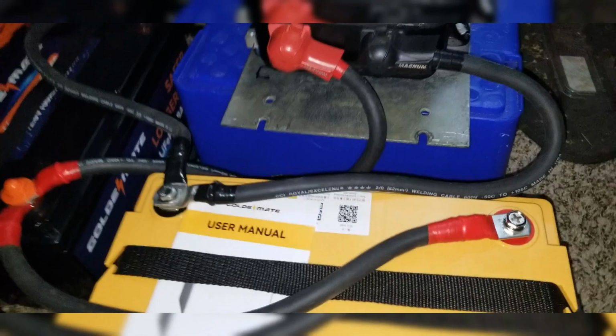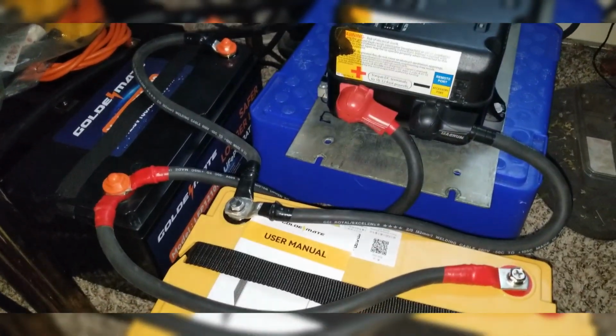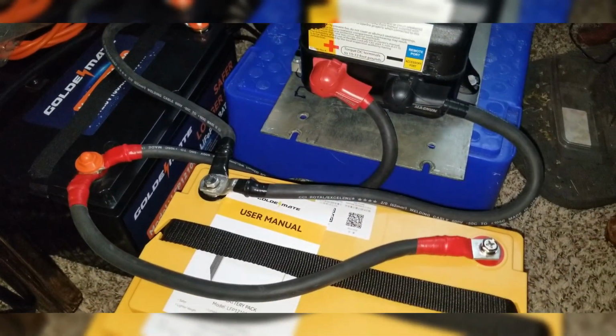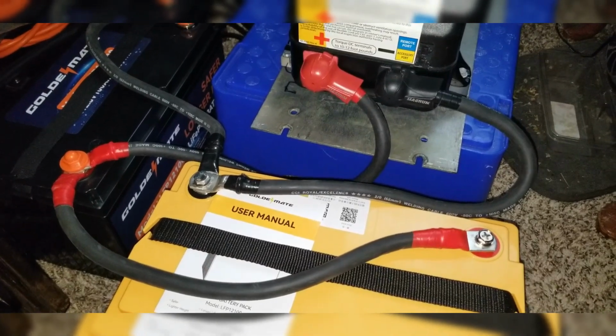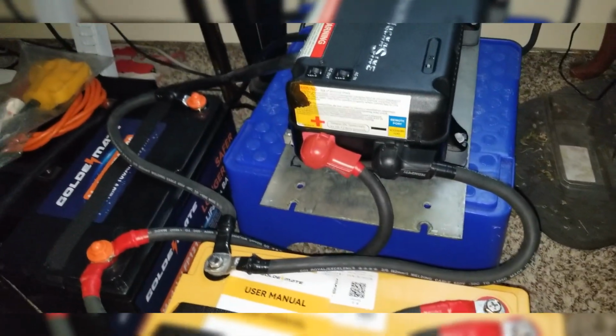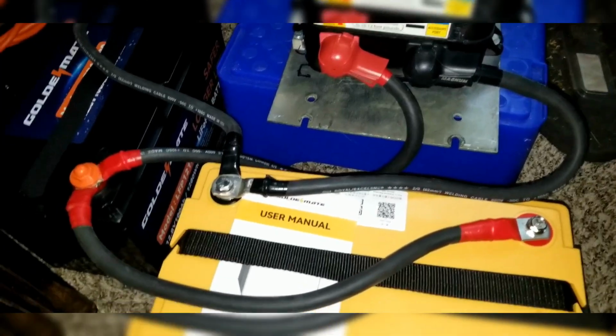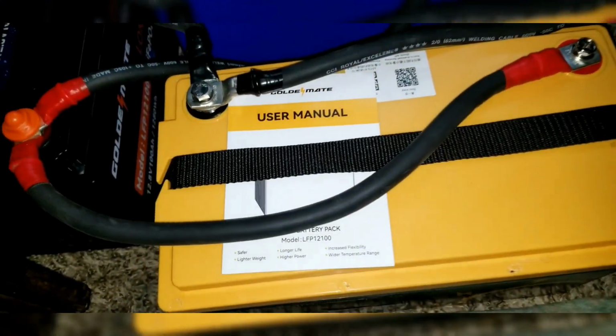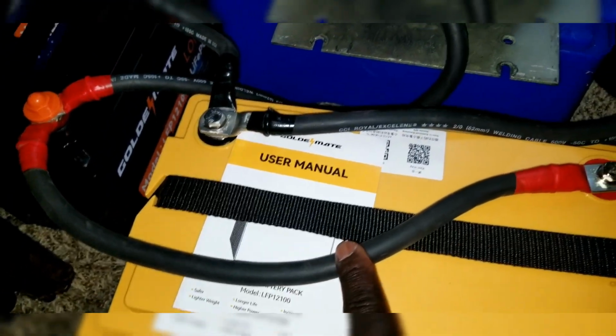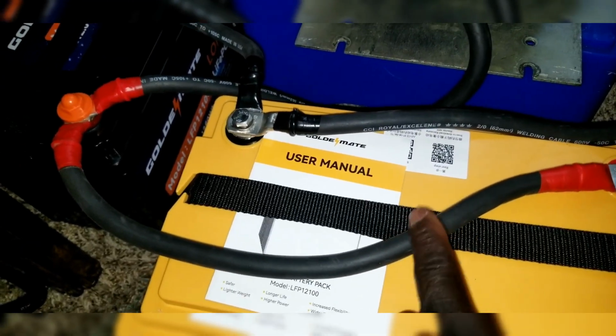It's good stuff. Because it's a 12-volt system, we want to make sure we pull in a lot of amps, and anytime this system surges, you can see it here on the monitor. So back to these guys, we use a beefy wire to transfer because it's low voltage and you can have a voltage drop.